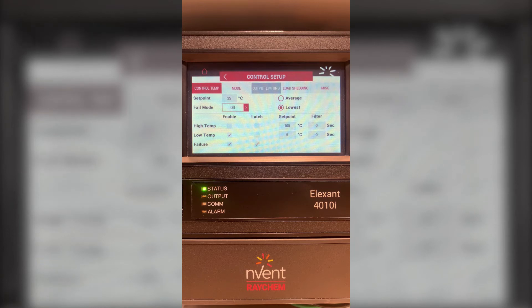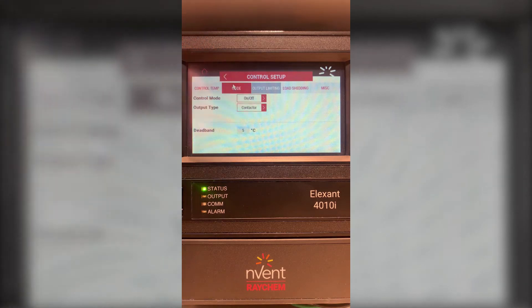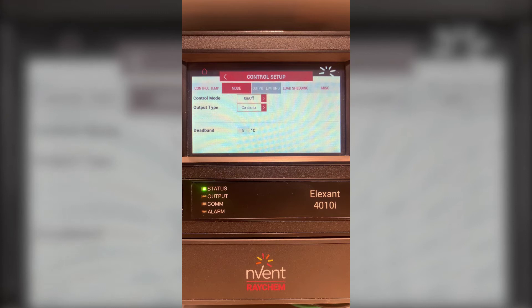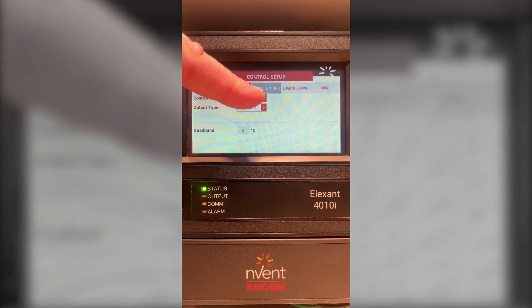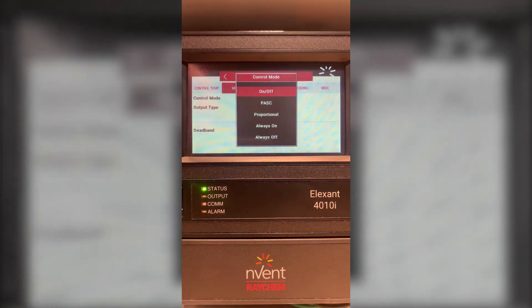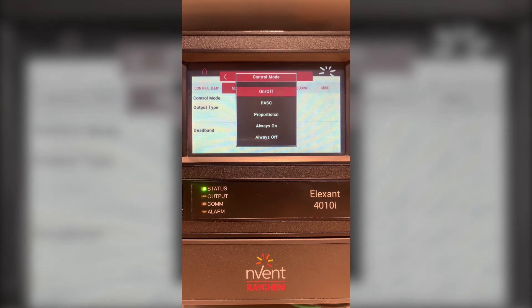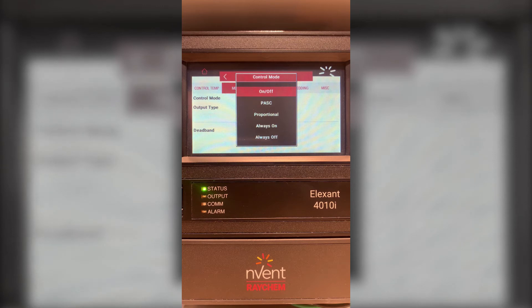Next I will choose mode. In the mode you have the control mode which is by default on off. However depending on your application you can choose PASC, which is proportional ambient sensing control, proportional always on, or always off. For this demonstration I will keep it at on off.